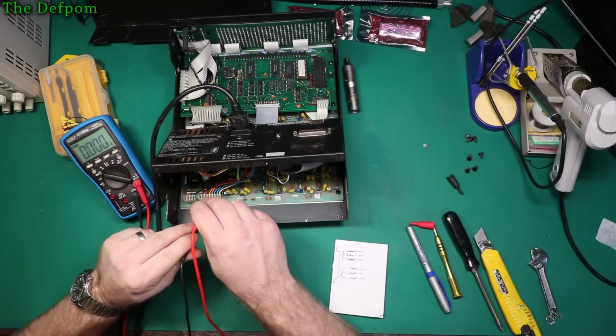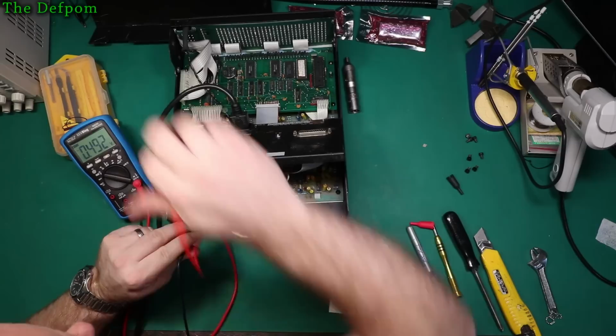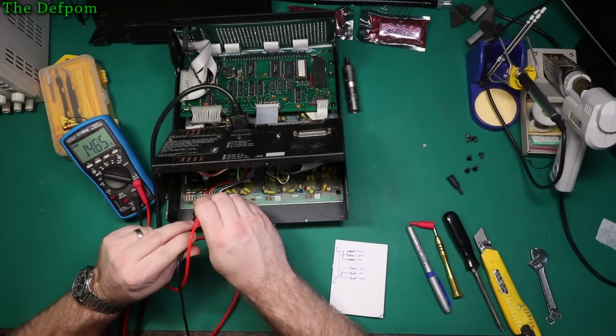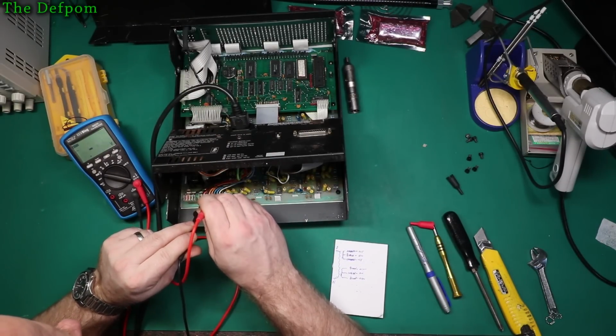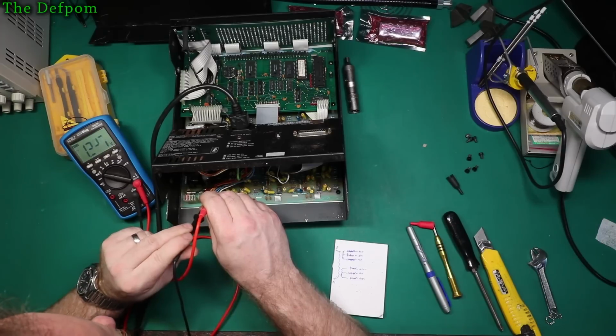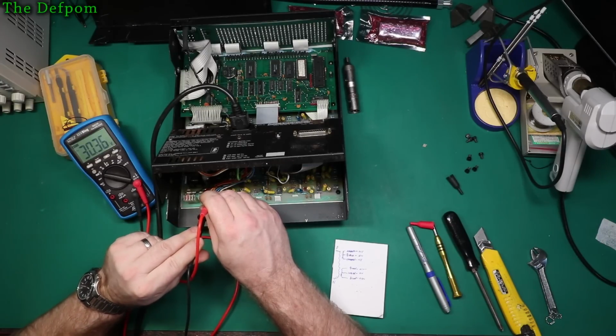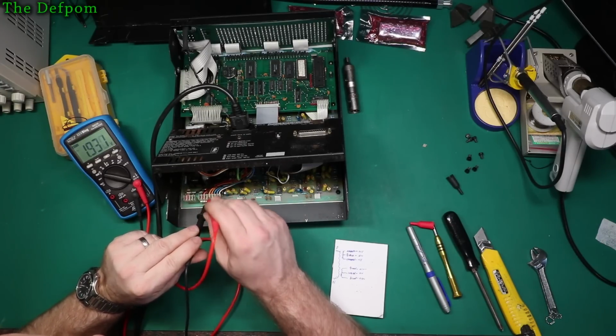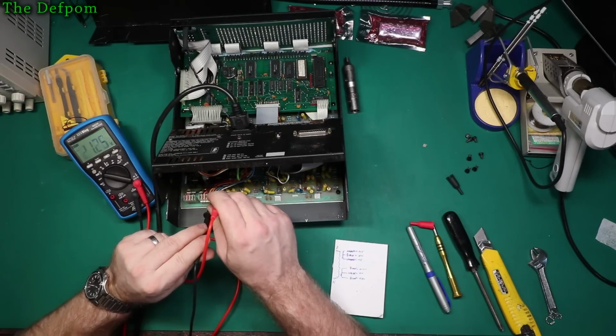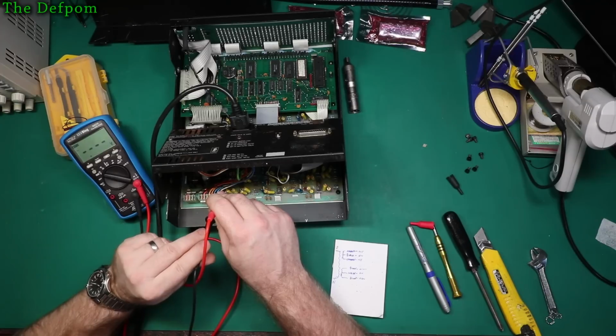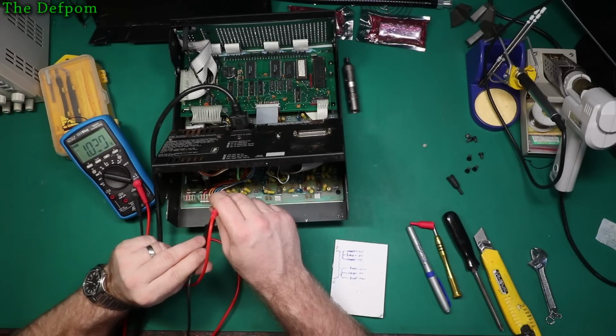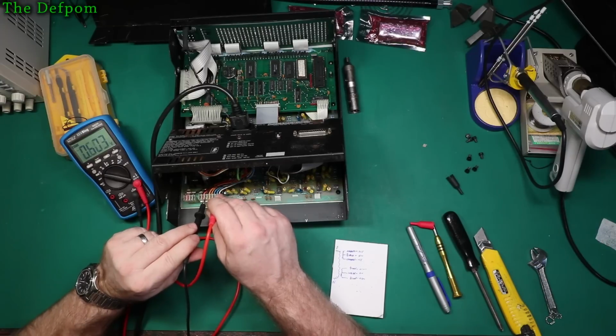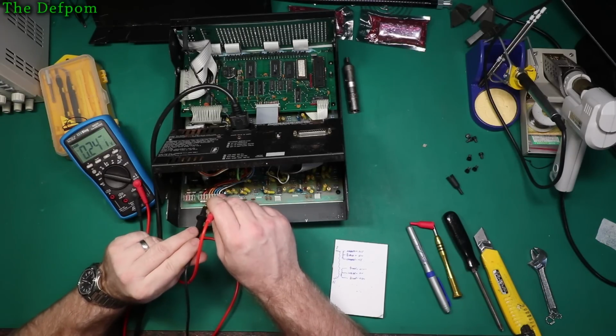Now if I measure from here to the orange, I'll turn it on. Getting 15 volts that side, 15 volts that side. If I go orange to orange, I get 30 volts. So that's a center tap winding, 30 volts. Blue to blue, also getting a voltage, 21 volts there. And if I go to the white, I'm getting 10 volts, 10.7, both of them. So the white is center tap. Also the white and the black are linked together, so I can use either one to make those measurements. I think they're linked together on this board.